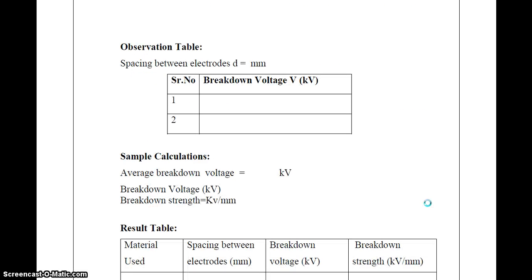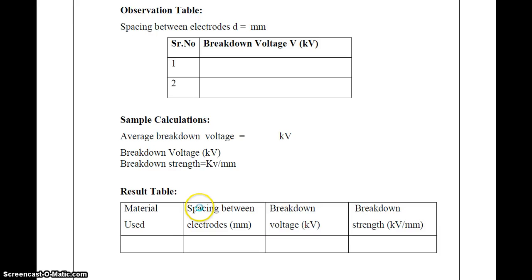Then next is the observation table: observation table on breakdown voltage, breakdown strength and dielectric strength. Then we have taken the reading of breakdown voltage between two electrodes with gaseous insulating material. Then the calculation is based on the average breakdown voltage for the gaseous insulating material. The breakdown voltage is in kilovolts. Then breakdown strength is the ratio of breakdown voltage in kV to the gap distance between the two electrodes in mm. The breakdown strength unit is kV per mm.